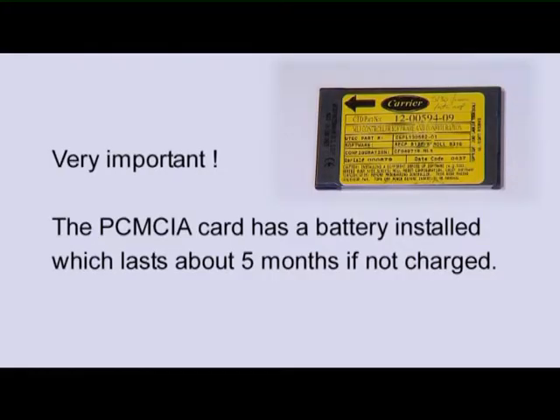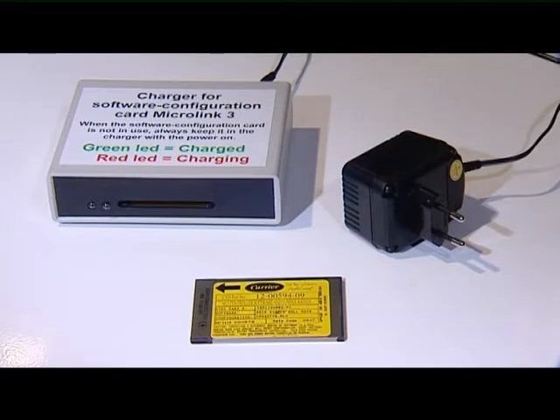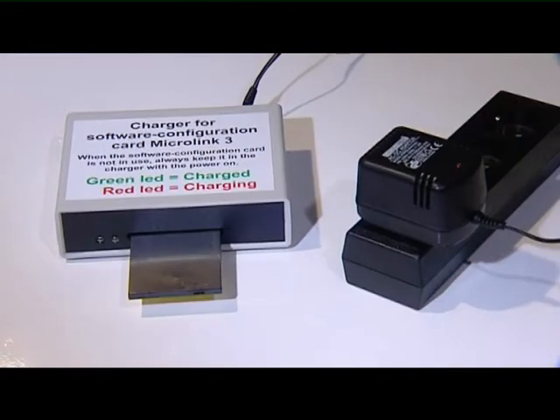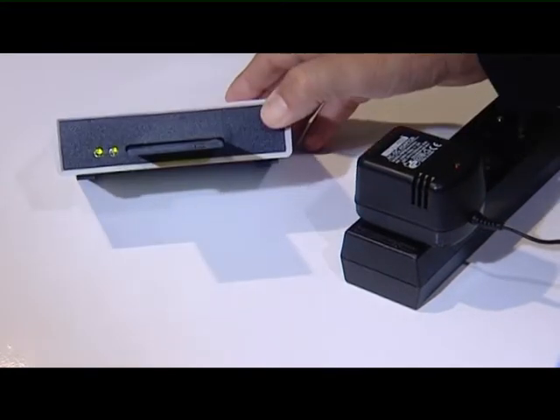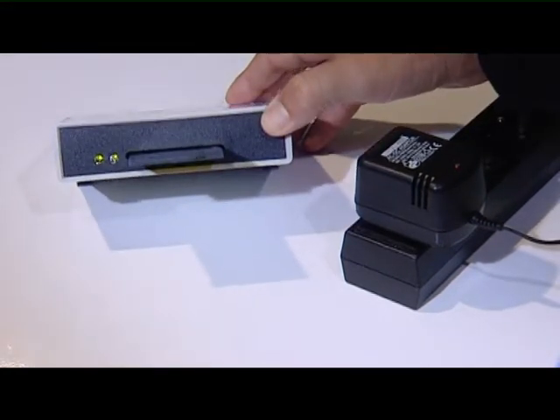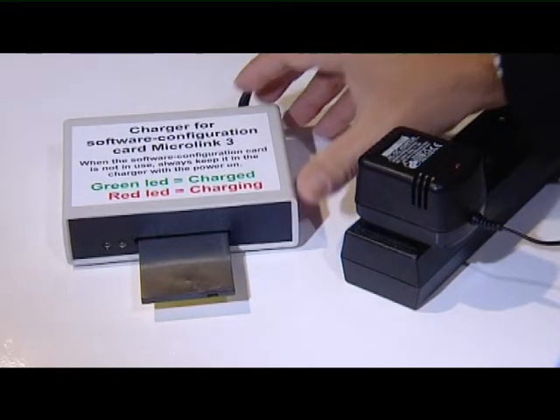Very important. The PCMCIA card has a battery installed which lasts about 5 months. If not charged, all the software installed on the card will be lost. It is not possible to reinstall software on the card on the vessel. To avoid this problem, the vessel will be supplied with a card charger as well. The PCMCIA card has always to be placed into the charger, which has to be constantly running on power. In this way, the card will be always ready when needed to program controllers.